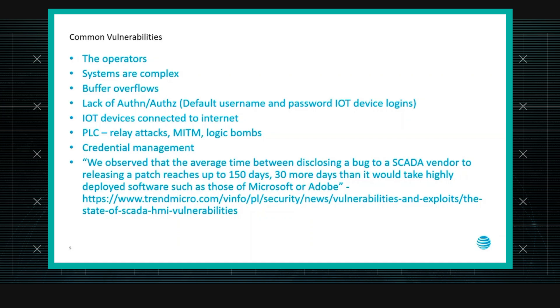Many PLCs are still susceptible to buffer overflow attacks. Being older and infrequently updated, they are also vulnerable to memory corruption attacks, which can be fatal to the system. Adversaries can use these to take down a system via DDoS, or gain remote access or a remote shell, then move laterally throughout the industrial control system.